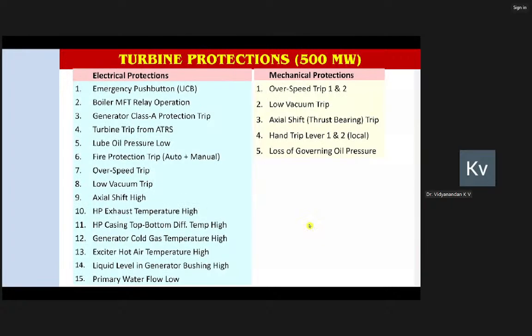Now, typically, a high capacity steam turbine, whether it be 500, 600, 800, etc., usually has 20 to 24, even more protections, because these protections have not been incorporated in a single day. These are all historical. If you consider the earliest turbine, some 140 years back when Charles Parsons introduced the turbine, there were not many protections available. Even till World War 1, protections in steam turbines were very, very few.